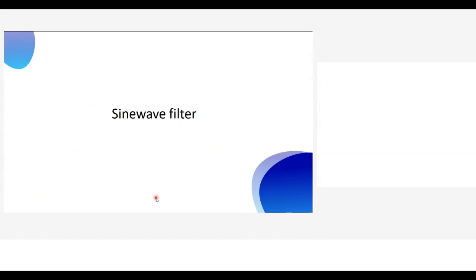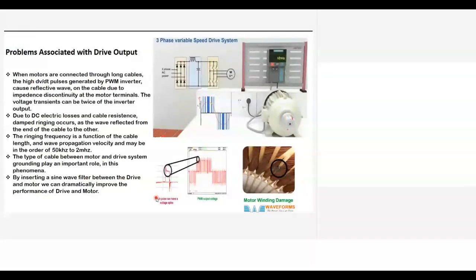So I come to the last part, the sine wave filter. This has nothing to do with the input harmonics that is fed into the source. This is basically, I think, very important for energy management, because I am sure you would have seen drives in one place and motors 2,000 meters away, or 1,000 meters, or 500 meters away. So what happens is the output of any drive is a square pulsed waveform, because of IGBT switching, which we may switch from 2 kilohertz to 8 kilohertz.